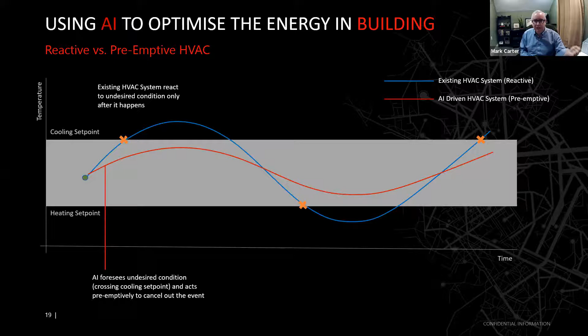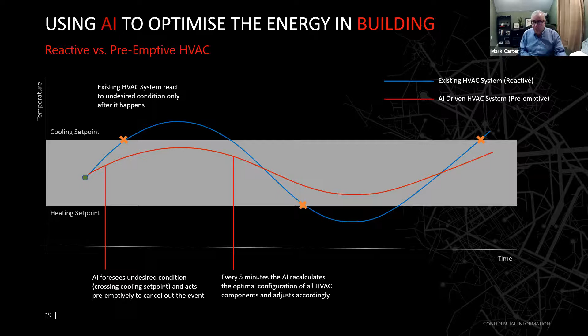But what you can do now is I don't have to wait for 45 minutes to know that that temperature is going to exceed its cooling set point. I can actually start making micro adjustments now to try to keep that temperature within the deadband. So now instead of the deadband being an area where you don't make any control, you actually are making controls to try to keep it within there for the maximum amount of time. So every 5 minutes, it's looking at the data, it's looking at its projections, and then making a whole new fresh set of control moves. And that's really basically at the heart of what an AI system can do.